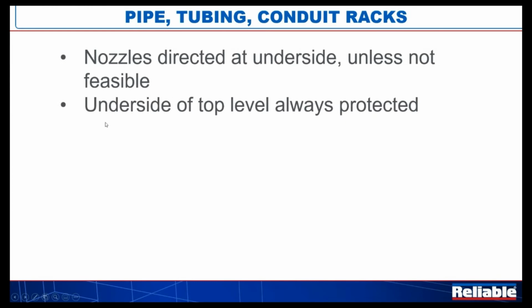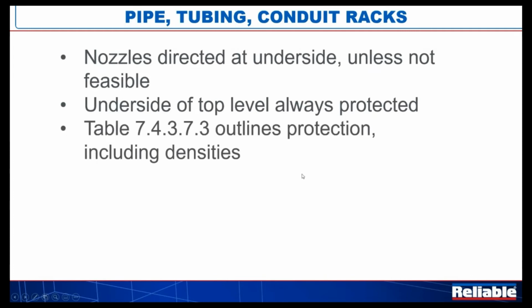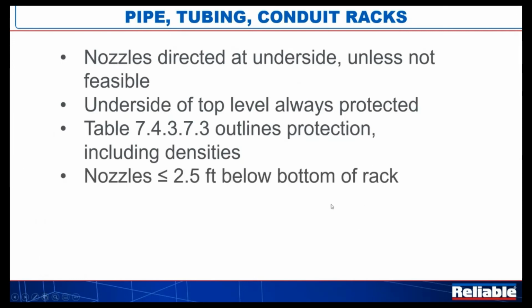However, if you have multiple levels, the underside of the top level, regardless of what's happening above it, must always be protected. And then there's a table, 74373, which is not a very long table, but it says, for instance, if you have 6 levels, you protect the alternate levels with a 0.15. Don't quote me on those, but look at the table. It will tell you, do I have to do every level? If so, what density? Do I do every other? If so, what density? You've got some options in terms of these multi-layered cable trays.